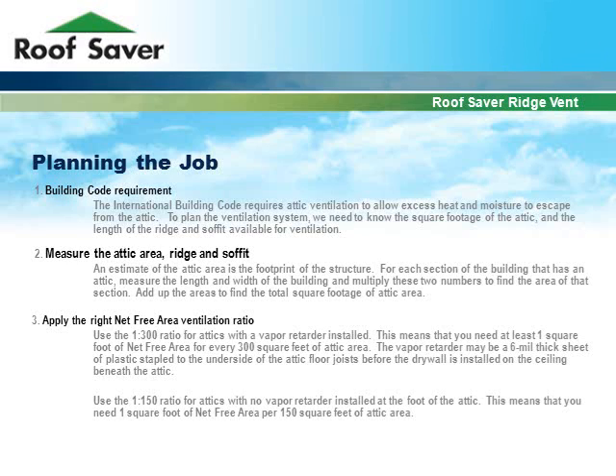Use the 1 to 300 ratio for attics with a vapor retarder installed. This means you need at least one square foot of net free area for every 300 square feet of attic area. The vapor retarder may be a 6-mil thick sheet of plastic stapled to the underside of the attic floor joists before the drywall is installed on the ceiling beneath the attic. Use the 1 to 150 ratio for attics with no vapor retarder installed, meaning you need one square foot of net free area per 150 square feet of attic area.